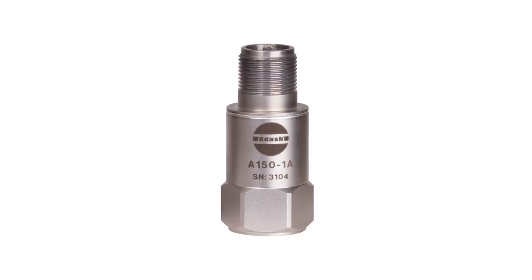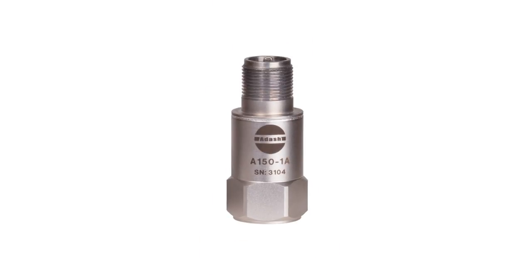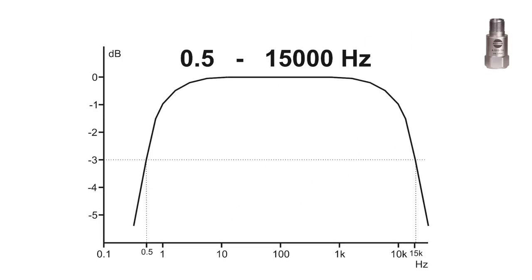This is a most common accelerometer with 100 mV per G sensitivity. The frequency range declared by producer is from 0.5 Hz to 15 kHz with plus/minus 3dB bias. Many people think that plus/minus 3dB is not too much.